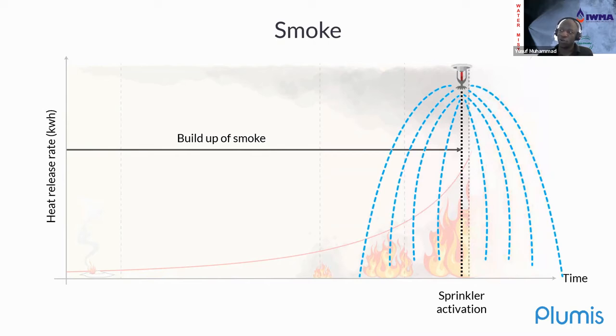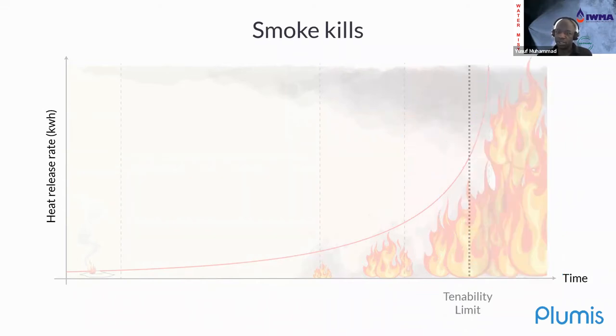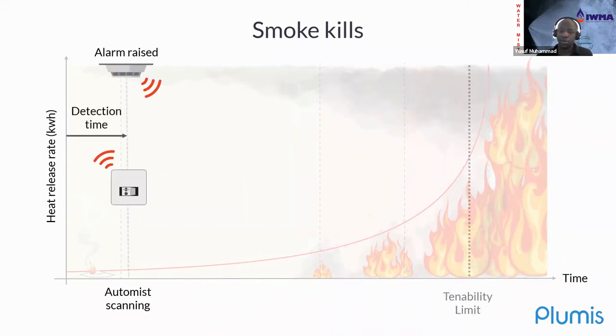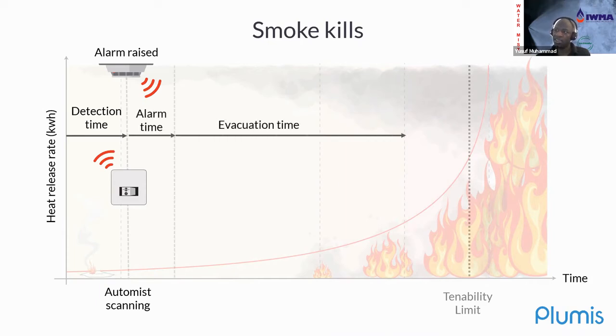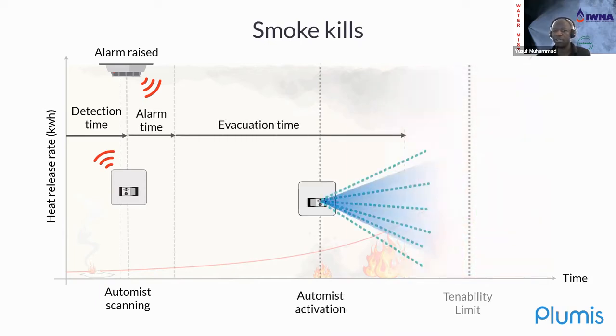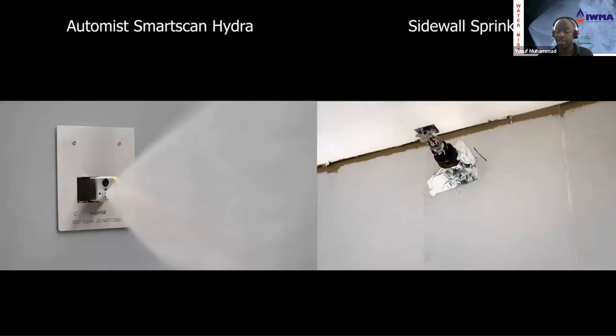particularly when you're triggering your suppression solely using heat, because you potentially have an incubation period where you're building up a lot of smoke within the premises, and you're also reliant on a significant buildup of heat in the room of origin before your system operates. What we're trying to do with our system is twofold. The first thing that we're doing is initiating that detection. That can be connected to a communication device to send a message. And the other thing that we want to do is operate at the earliest possible time, well within that tenability limit. Now, just to illustrate that, here we've got some testing which we did at the Fire Protection Association.